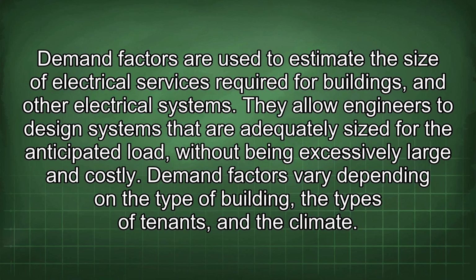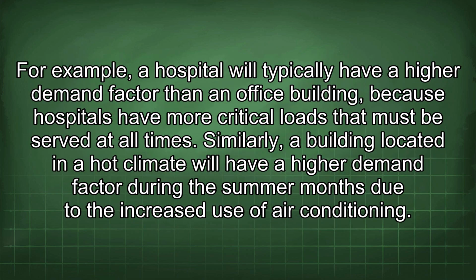Demand factors vary depending on the type of building, the types of tenants, and the climate. For example, a hospital will typically have a higher demand factor than an office building because hospitals have more critical loads that must be served at all times. Similarly, a building located in a hot climate will have a higher demand factor during the summer months due to the increased use of air conditioning.